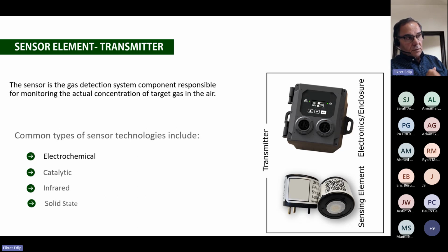The reason is that the technology being used is inexpensive to build, but the disadvantage is that it can detect any gas. It really physically can detect any gas. So in order to get it specific to a certain gas, you have to calibrate it for that target gas, and often that cannot be 100% accurate. And then you have catalytic sensors, typically used for combustible gases. And then the electrochemicals are accurate also. They are used for toxic gases such as CO, NO2, and refrigerants, etc.